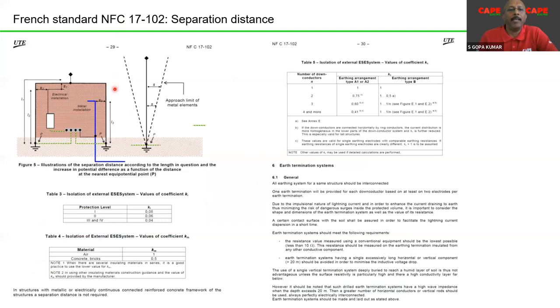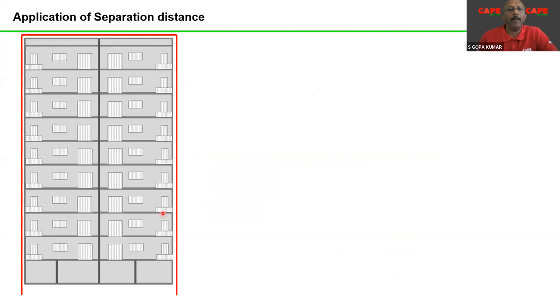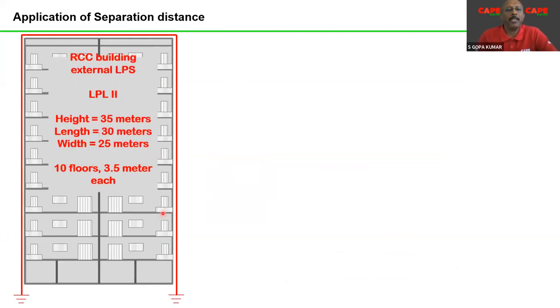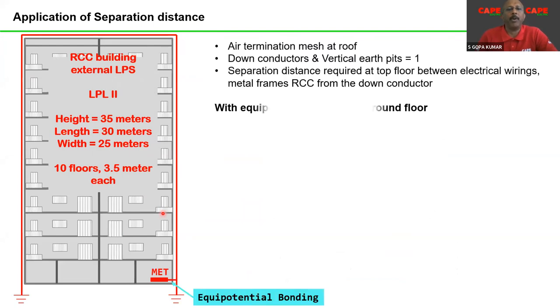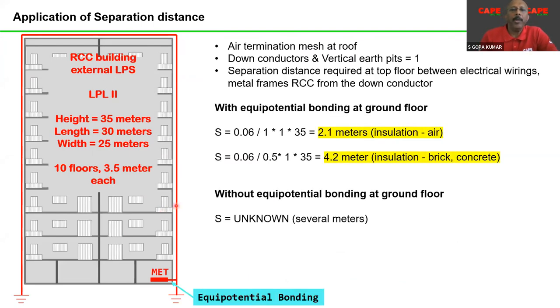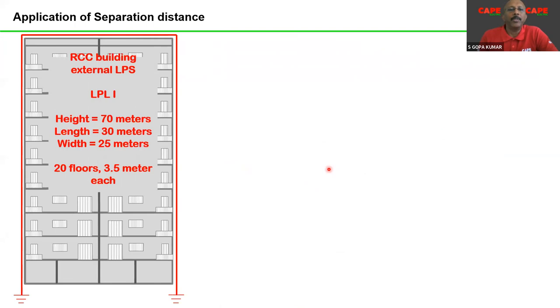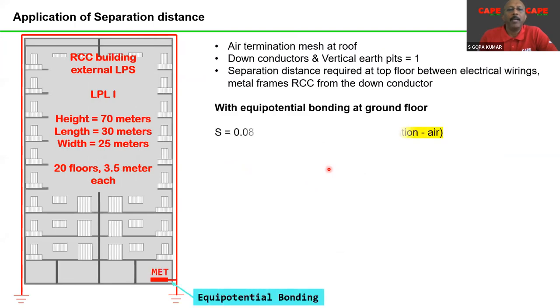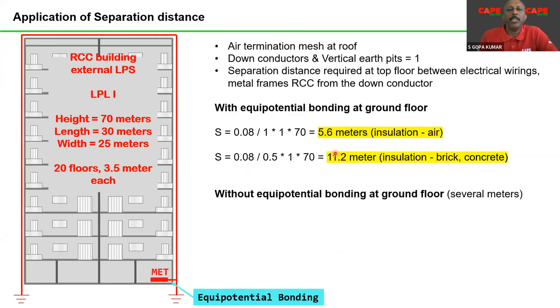Now, if we apply the same separation distance, you can find the same values in ALTS as well. If we apply the same separation distance for building number one, a 35 meter building with equipotential bonding, you get a value of 2.1 meter. The separation distance required for an ESE rod is double the normal. In brick, again, 4.2 meters. For a 70 meter building, the calculation says about 5.6 meter and 11.2 meter away from the building.